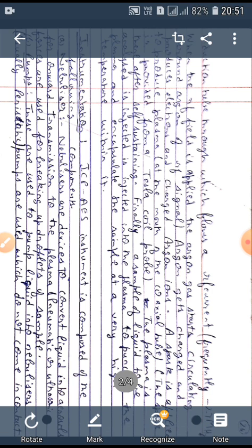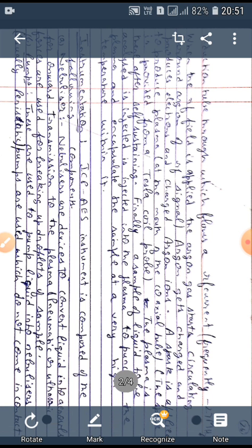When the RF field is applied, the argon gas starts circulating. Argon gets charged and produces electrons and charged argon ions. A spark is applied to produce plasma. The spark is provided from a Tesla coil probe. The plasma is thereafter self-sustaining. Finally, a sample of liquid to be analyzed is injected into the plasma to puncture the plasma and encapsulate the sample at a very high temperature within it. This is the basic principle involved in the ICP.